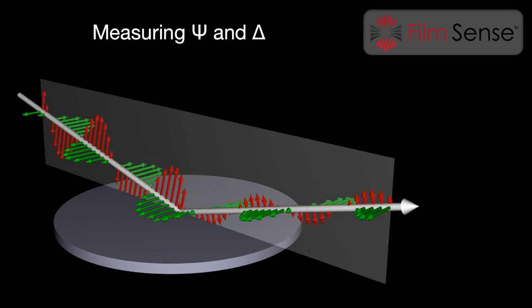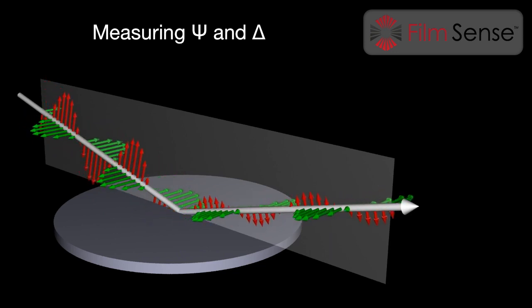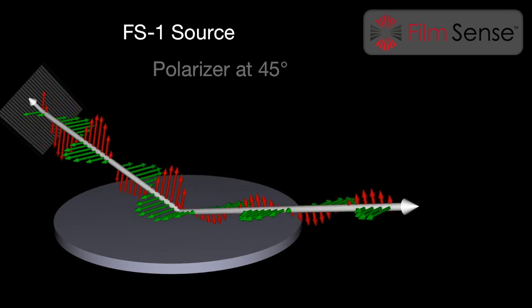To measure the ellipsometric parameters, an ellipsometer system must set the polarization state of the incident beam and detect the polarization state of the reflected beam. In the FilmSense FS1 ellipsometer, a polarizer in the source unit sets the incident beam to a linear polarization state, rotated 45 degrees from the plane of incidence.